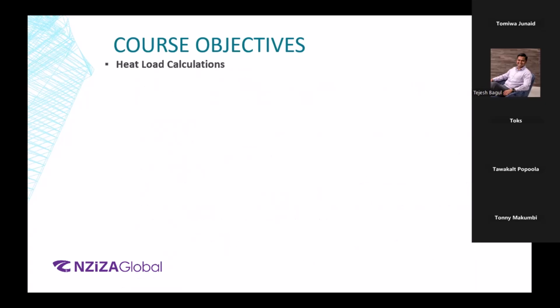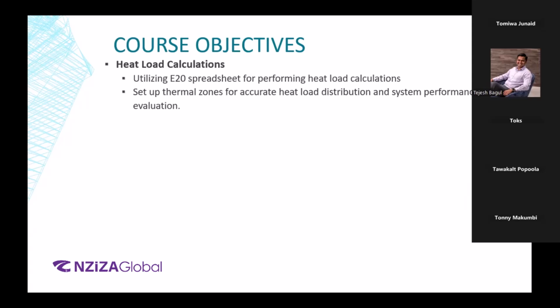After that, heat load calculations, basically the bread and butter of an HVAC engineer in a given trade. We'll look into that with an E20 spreadsheet. We'll make sure that we understand how we set up thermal zones to get the maximum possible efficiency and utilization from the HVAC systems that we are designing. Along with that, we'll also take a look at the ventilation calculations and the calculations that are needed for supply air as per the ASHRAE 170 standard.